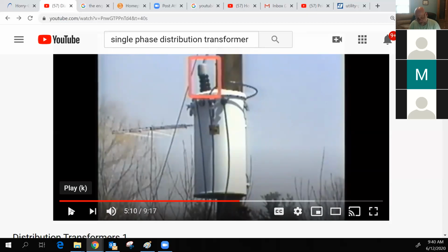Years ago, before we became Duke, this was much like what we used in the field. This transformer is a single bushing CSP transformer. CSP meaning completely self-protected. This transformer actually has a breaker inside on the secondary side, and you can see the little handle sticking off the side. And that was before we put primary fuses above the bushing on the primary side. What we did with that, if there was a secondary fault, it would actually be more like a breaker in your home, and it would automatically trip that breaker inside.